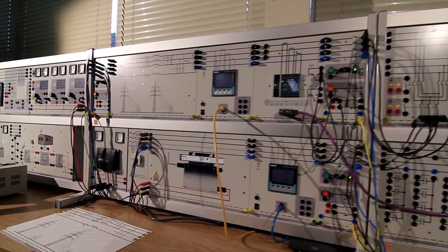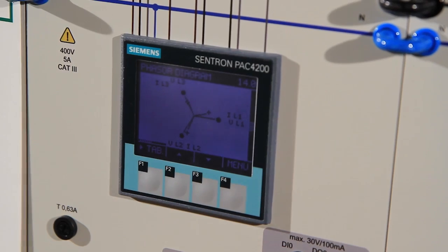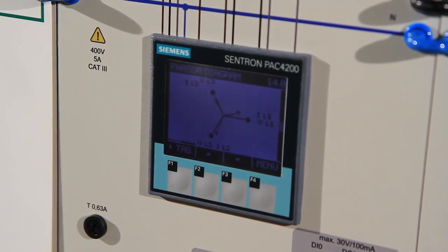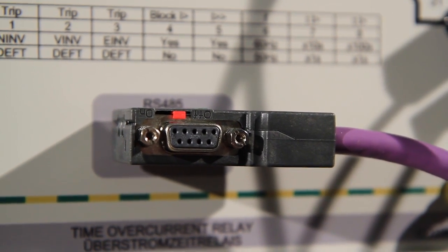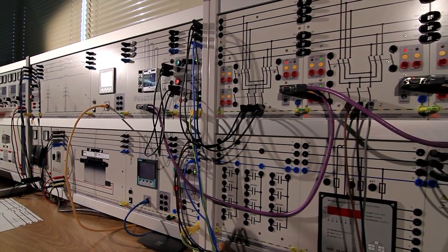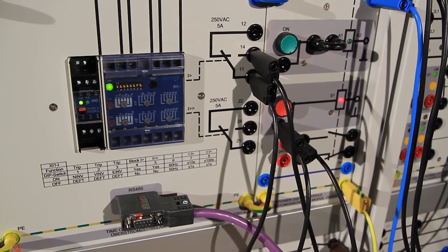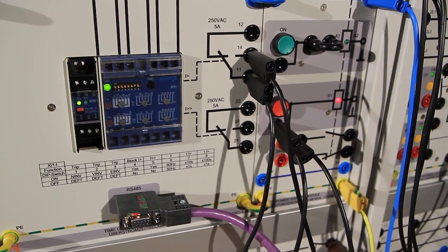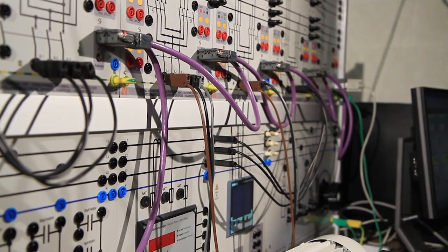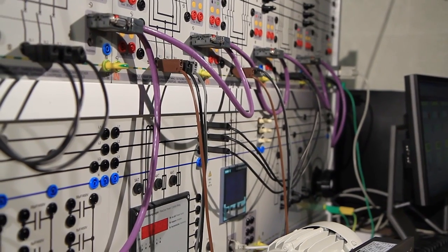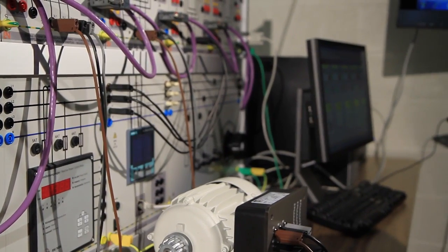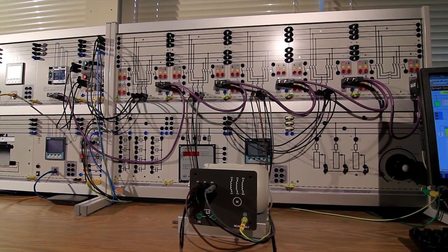The system is equipped with smart meters. They are all fully programmable and have long-term memory. One of the features of these meters is that they have TCP IP connection, so they act as sensors. The next element in the system is an overcurrent relay, which is also TCP IP enabled. Then the circuit breaker. One of the most important features of the system is a double bus bar system. You can reconfigure it based on the conditions of operations, and each load and each source has its own section.